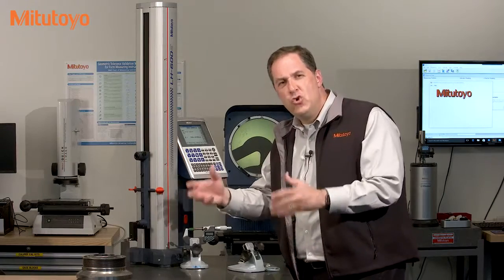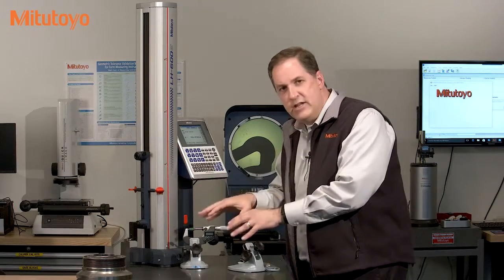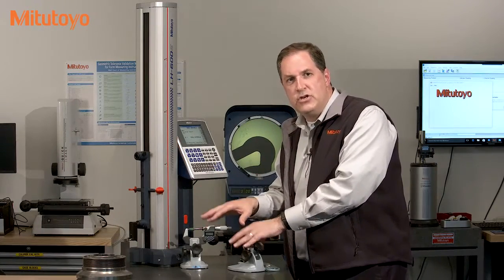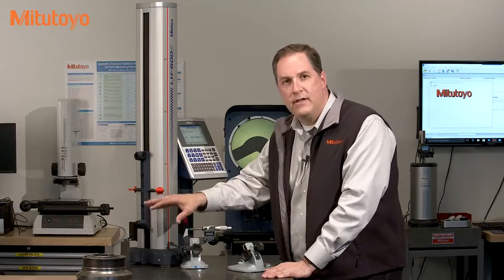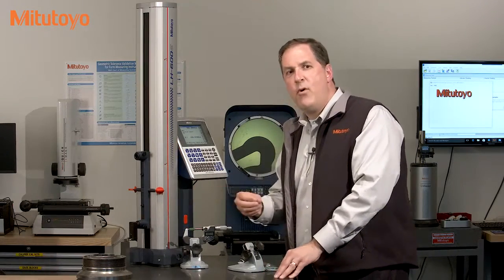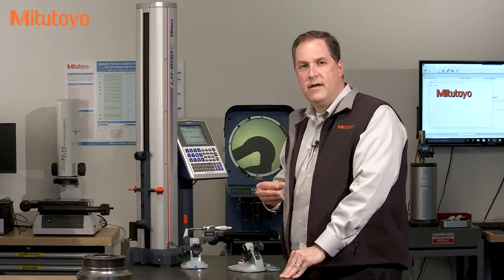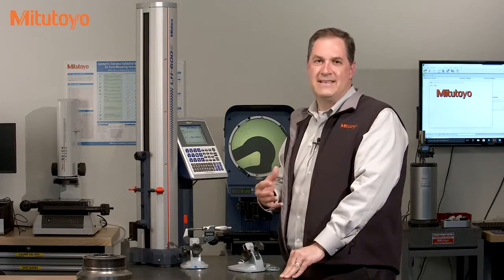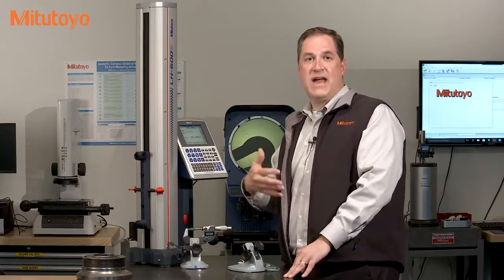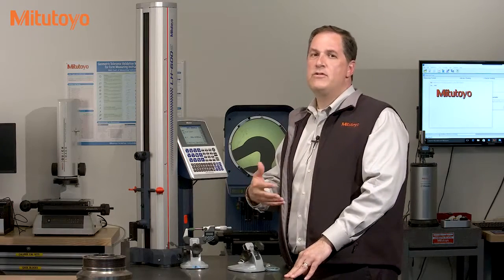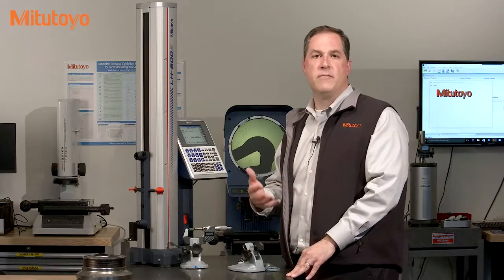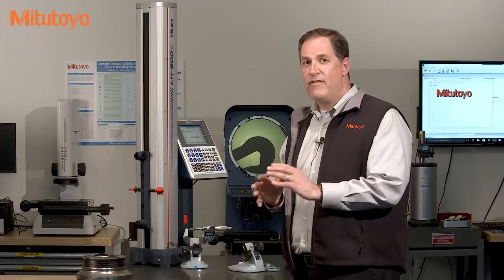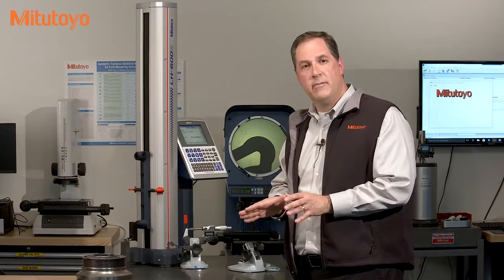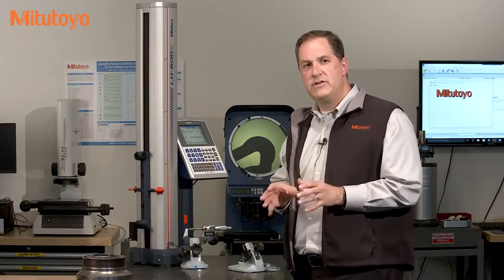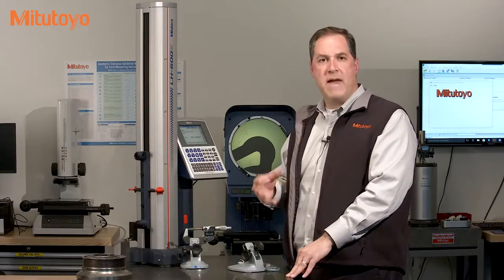All of these user calibrations, from setting 0 on the mics to determining the probe diameter on the linear height, are very important aspects of calibration, but they're typically not considered part of an official calibration. Rather, those are covered under proper use of the measuring equipment. However, they are very critical to making accurate measurements, and every organization needs a method to manage this properly.